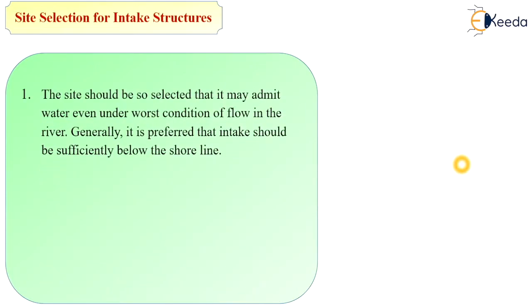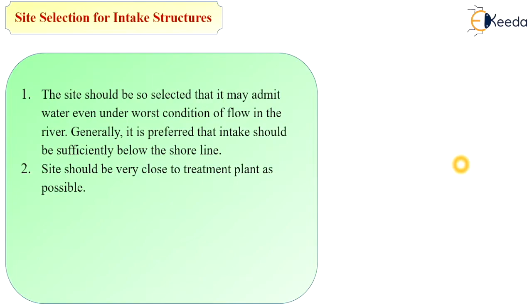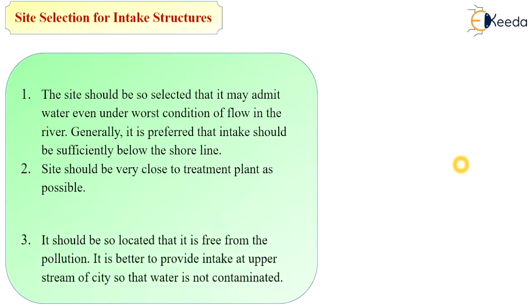Next are the site selection criteria for intake structure. The site should be selected such that it may admit water even under worst conditions of flow in the river. It is generally preferred that the intake should be sufficiently below the shoreline. The site should be as close to the treatment plant as possible so that we can reduce the cost of conveying water through the pipe.